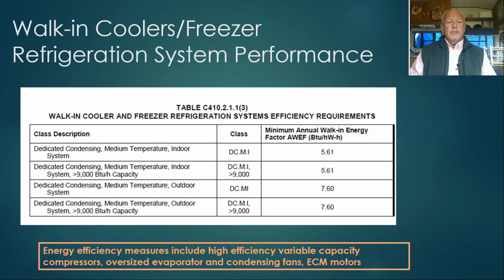And as I mentioned, the energy efficiency measures for these systems would include variable capacity compressors, oversized evaporator and condenser coils, and ECM motors on evaporator fans and condenser fans. Again, achieving anywhere from a 20 to 40% reduction in energy use for these systems.